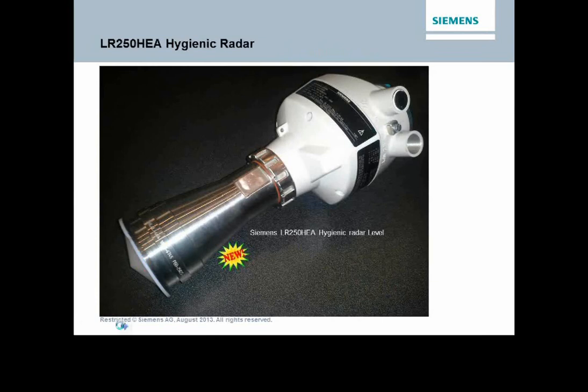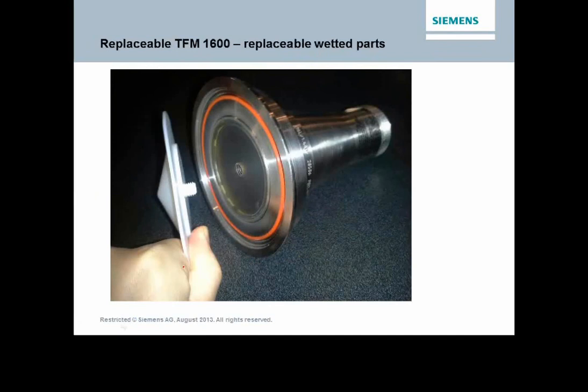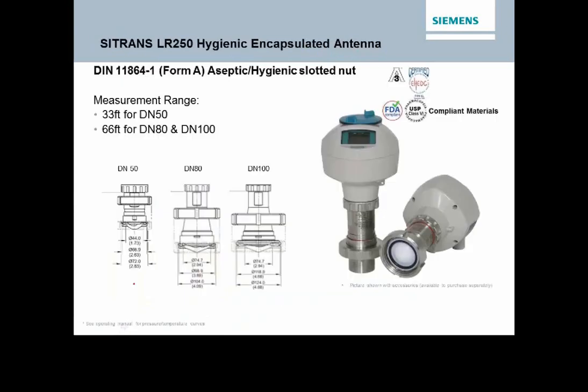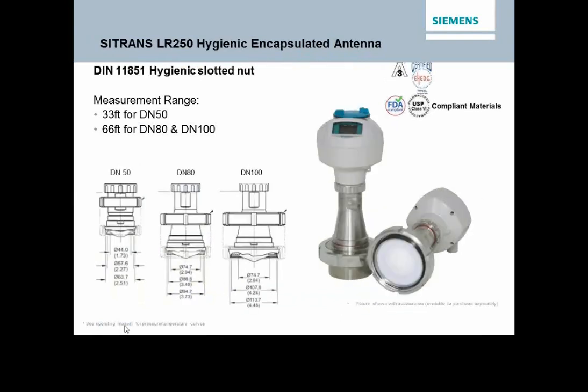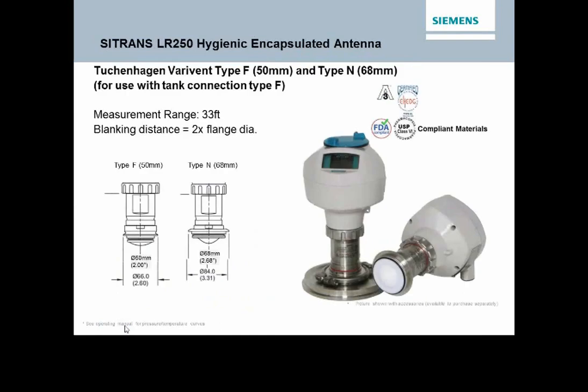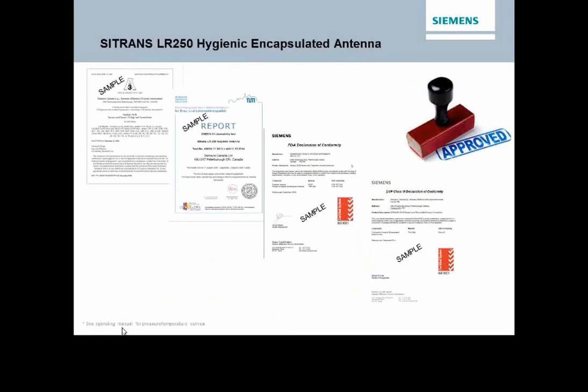That lens is also replaceable, okay? And so it's a gap-free system. We do meet ISO requirements for that. But we do have replaceable wetted parts. So if that part does get damaged, the whole unit does not have to be replaced. That lens itself can be replaced. We talk about aseptic and hygienic slotted styles. Hygienic slotted nut and the Tuchenhagen style. All these are designed from the process of getting all the approvals, both for Europe and for the States.